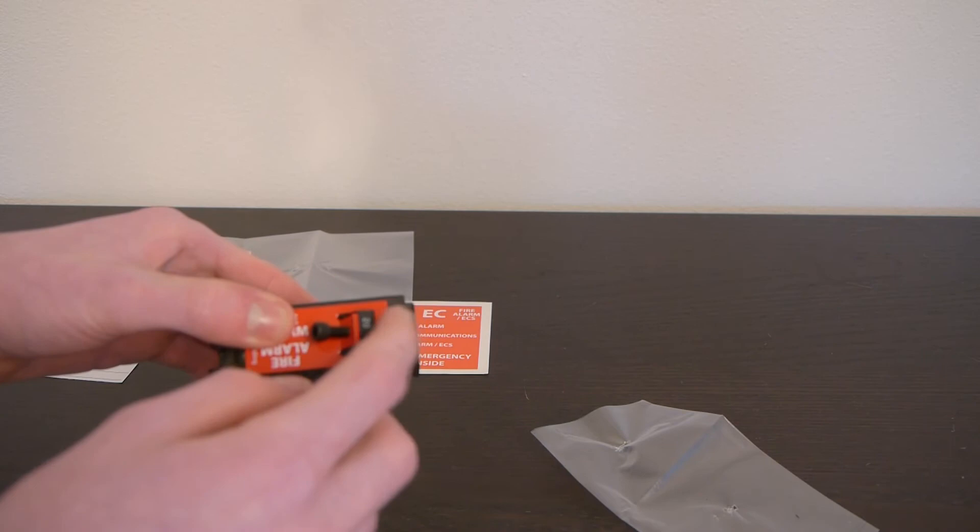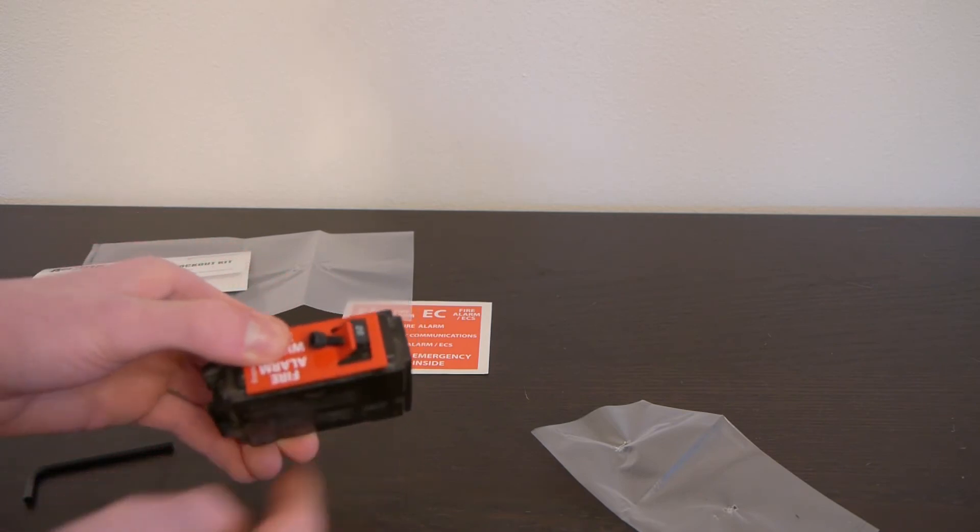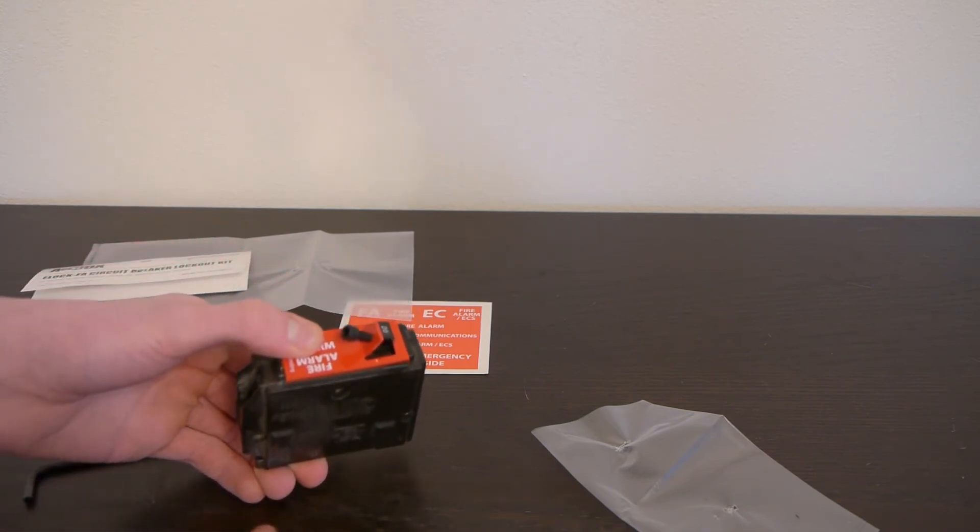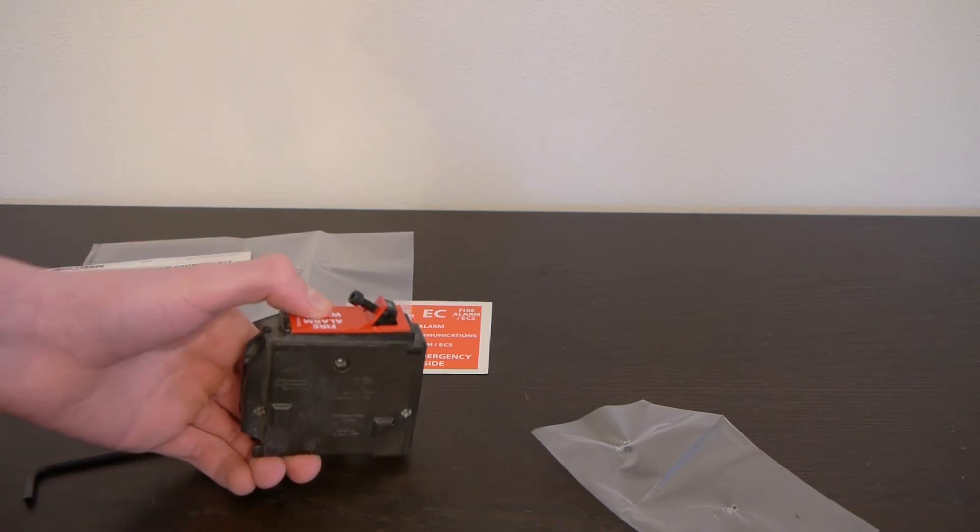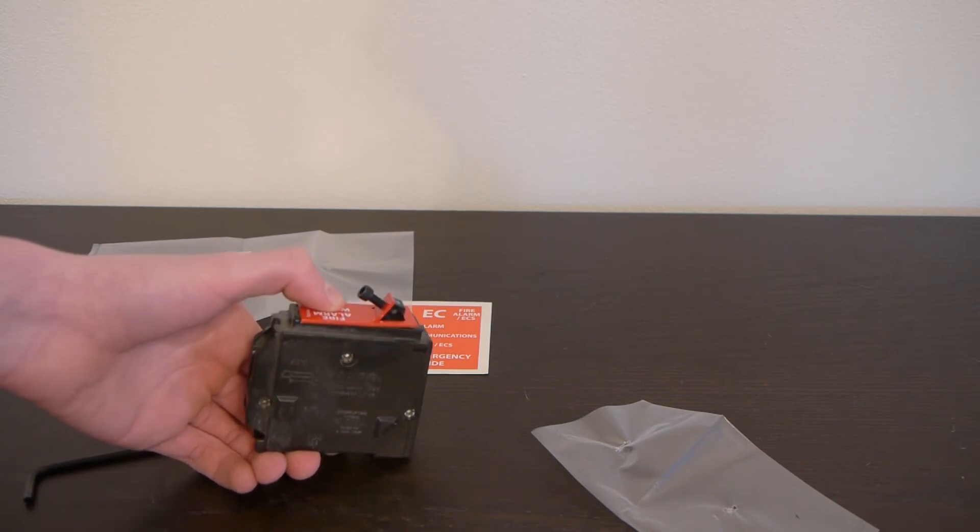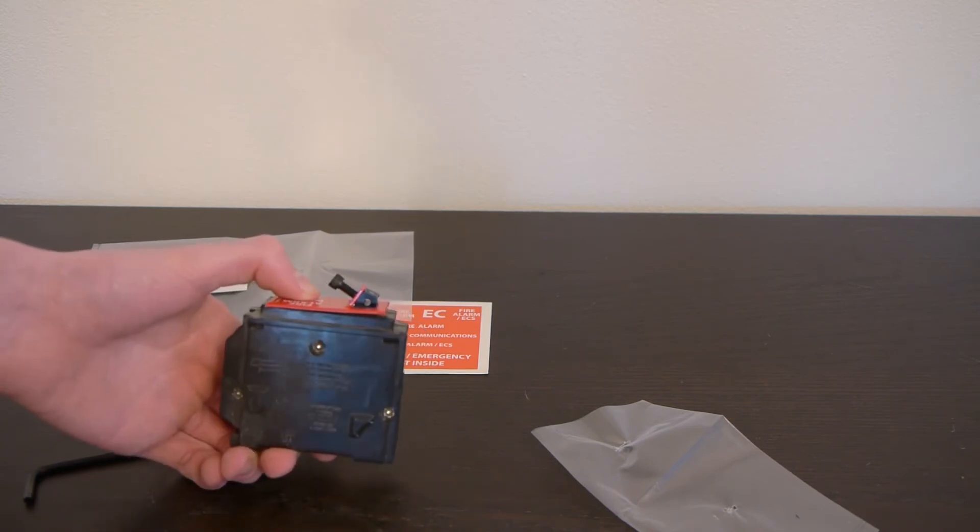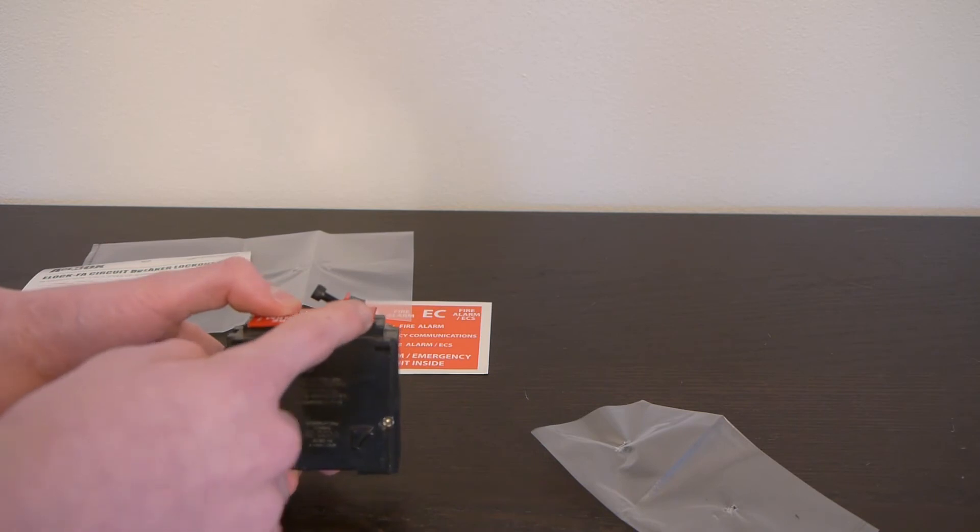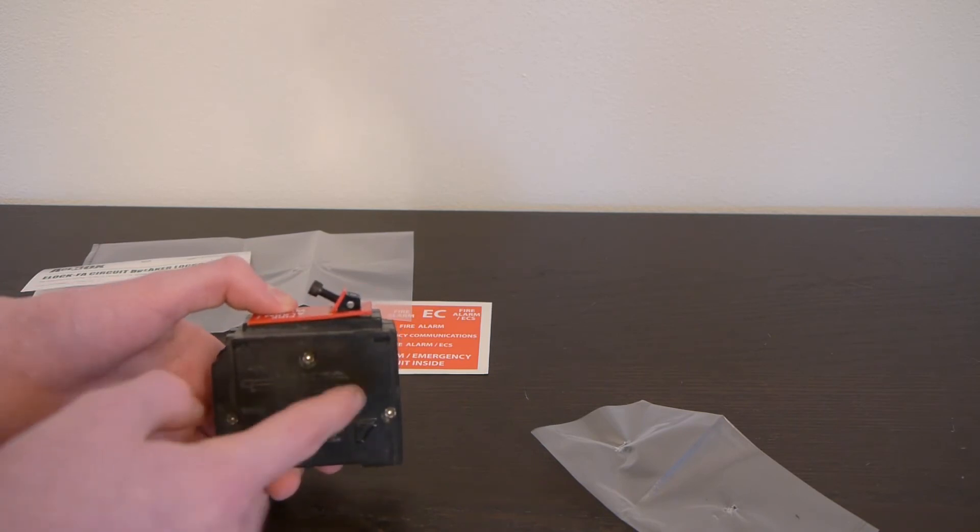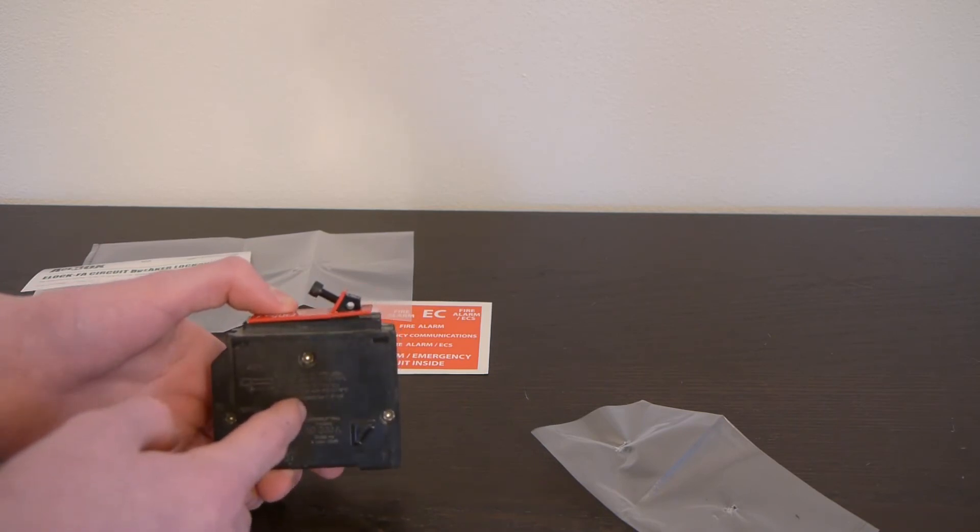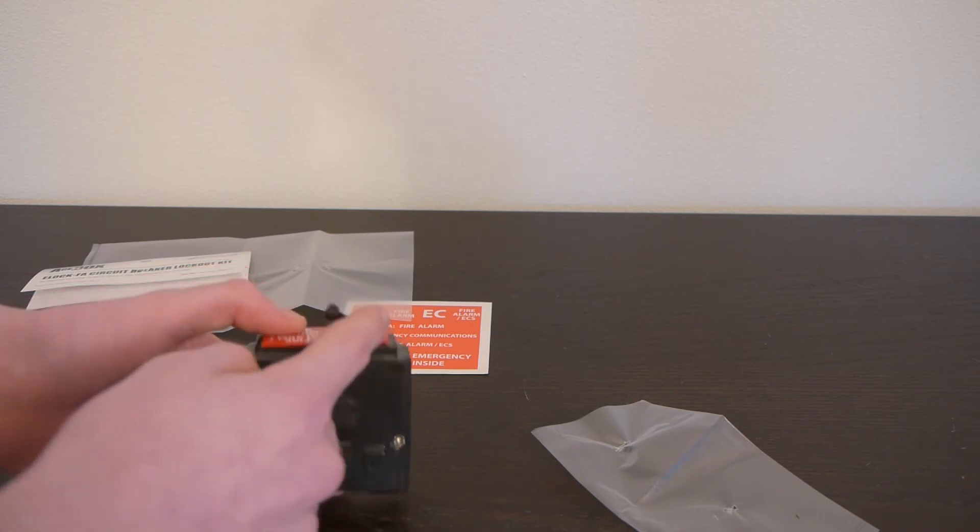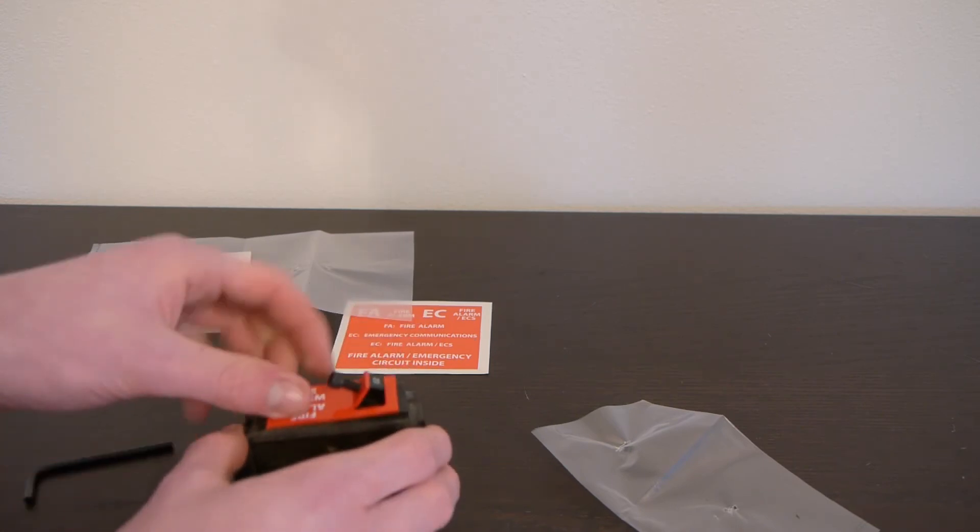So that prevents the breaker from being turned off. And you might be wondering, why would you want to make it so your breaker couldn't trip? If there was a fault, you could burn up your wiring and stuff. Well at most modern breakers, this handle can actually be held on, and if there's too much current and it trips, it'll actually internally trip, but the handle can still stay in the on position.